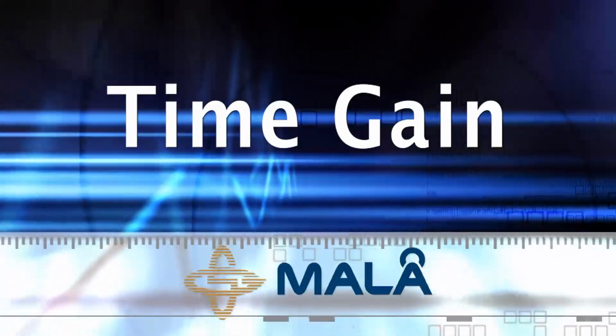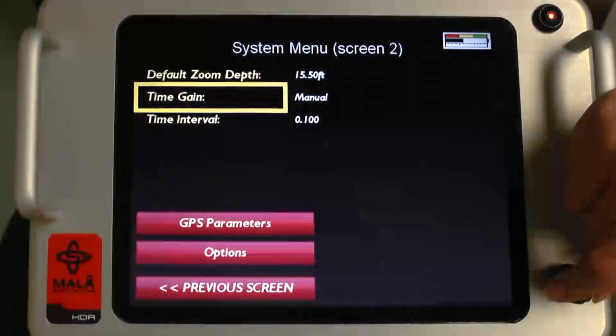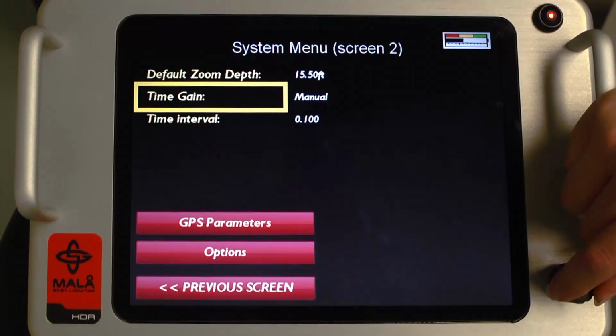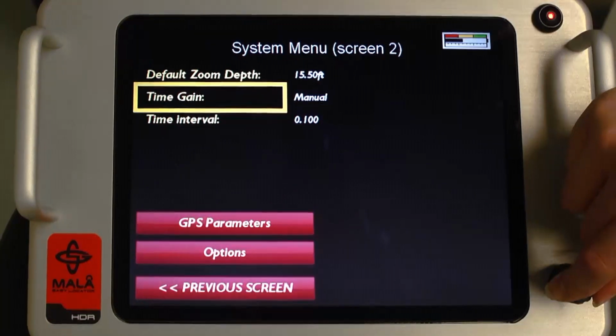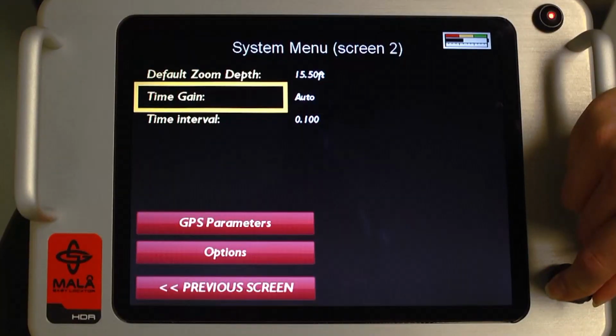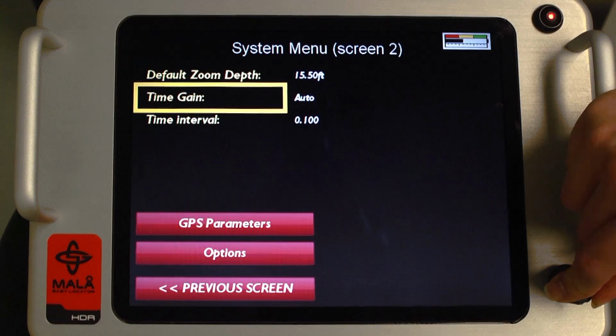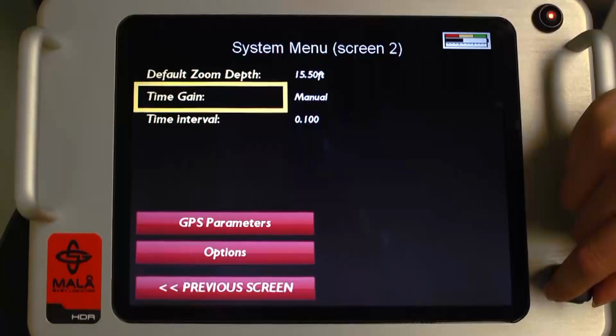Time gain. The time gain button is used to adjust the time gain for the GPR profile. The control knob is rotated to increase or decrease the applied time gain. The user may select either manual or auto by depressing the control knob. Soil conditions dictate which mode is most effective. Auto gain amplifies the signal with coefficients that balance the signal throughout the radargram. Manual gain is used to manually amplify the time gain on the GPR profile.